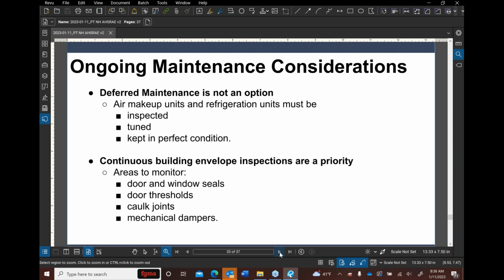Mechanical dampers, that's actually a really interesting story. So I mentioned we would talk about this. Part of the PHIUS requirement was to do a blower door test during construction. And initially our building actually failed the first blower door test. What we found out was that the exhaust dampers within the DOAS units were being forced open by the blower door testing equipment. Oh, I see. And we were losing air through the exhaust dampers. So we had to add some points to the BAS system and add motorized dampers that when the unit was running, it actually drove the damper shut instead of just passively falling shut. So that was kind of a lesson learned.